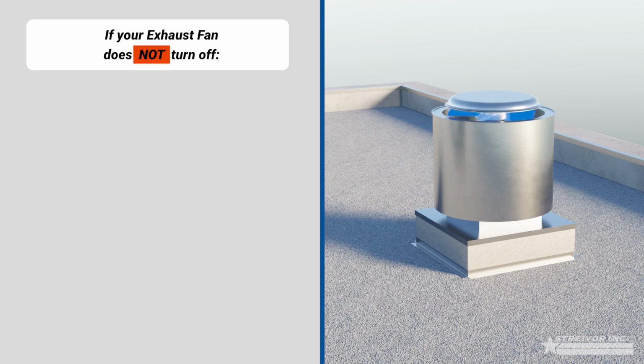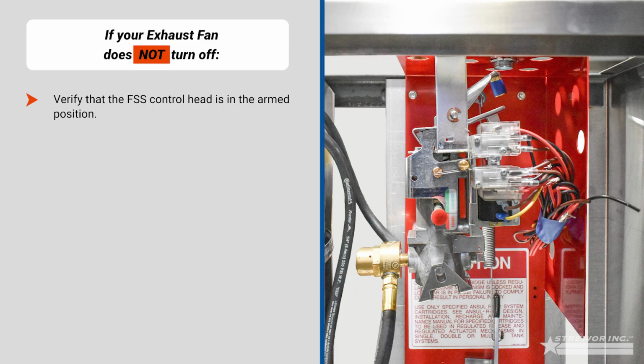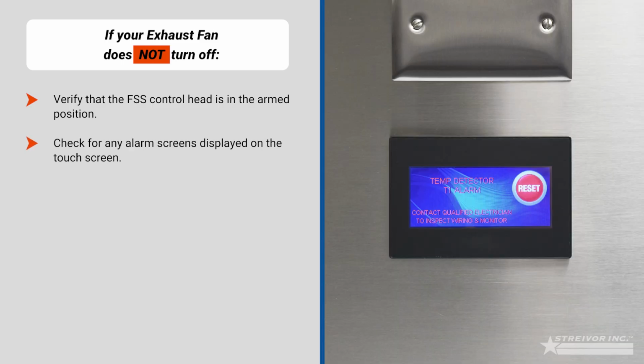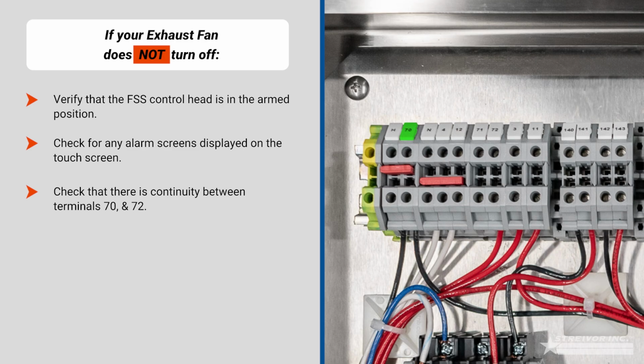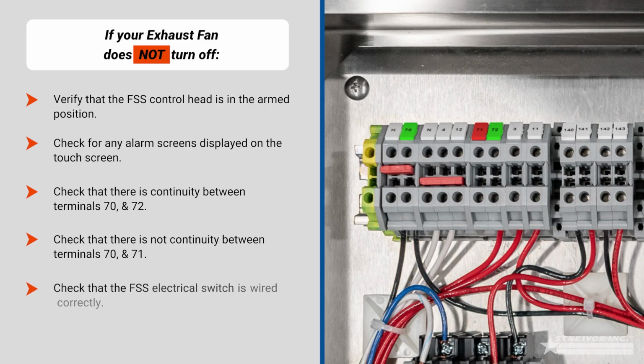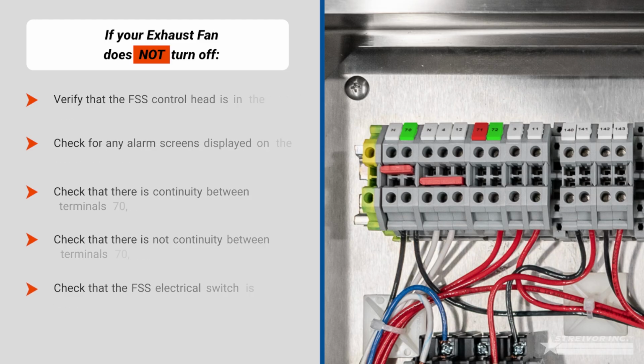If your exhaust fan does not turn off, verify that the FSS control head is in the armed position. Check for any alarm screens displayed on the touch screen. Check that there is continuity between terminal 70 and 72. Check that there is not continuity between terminal 70 and 71. Check that the FSS electrical switch is wired correctly.